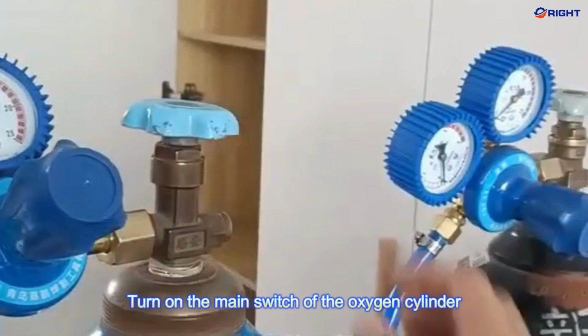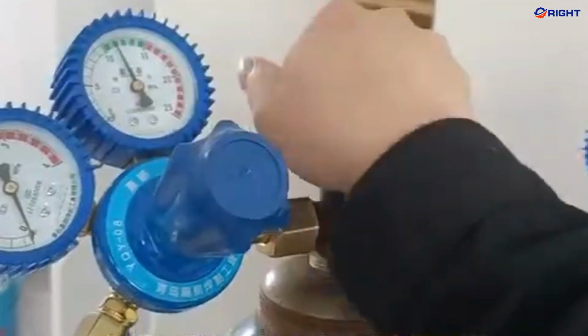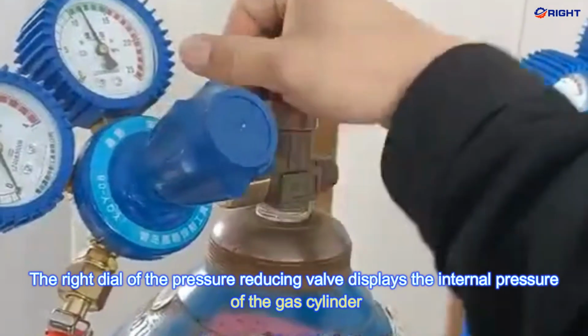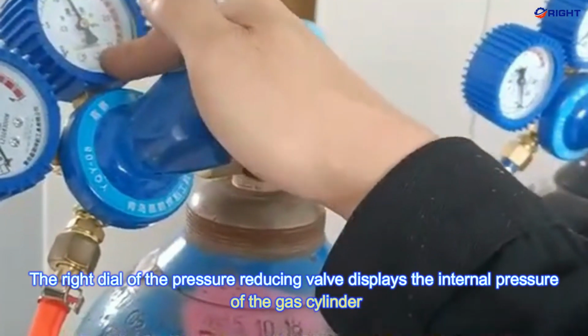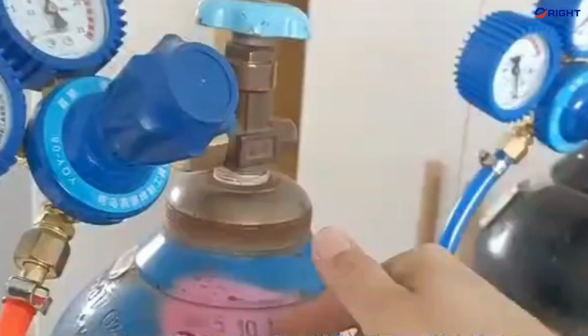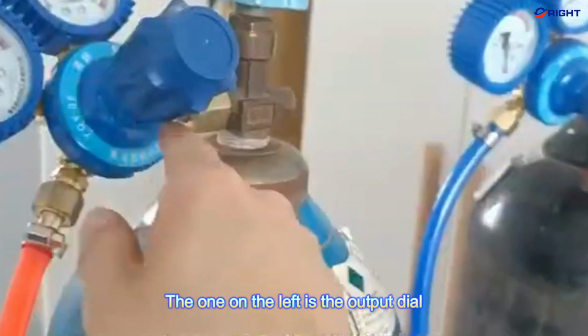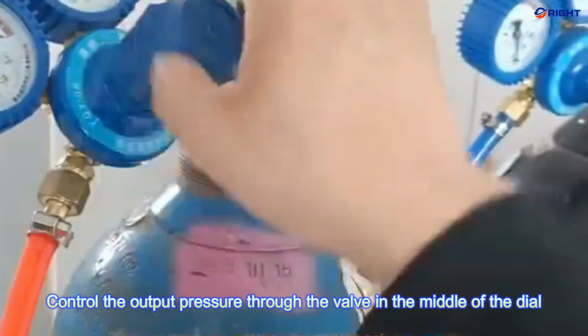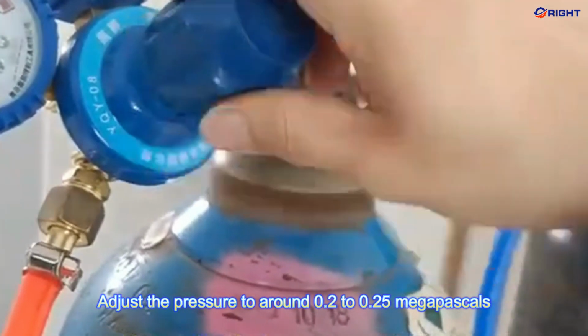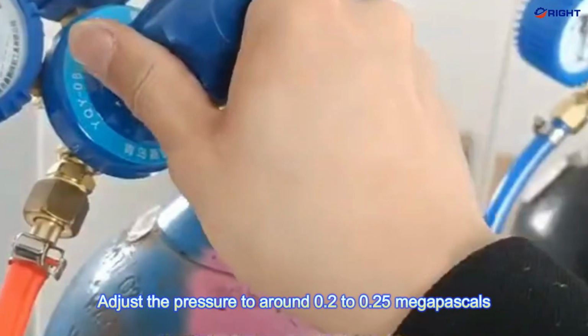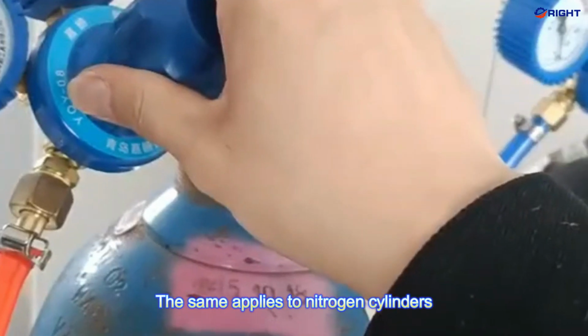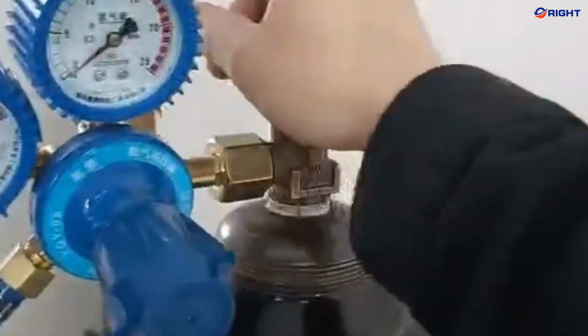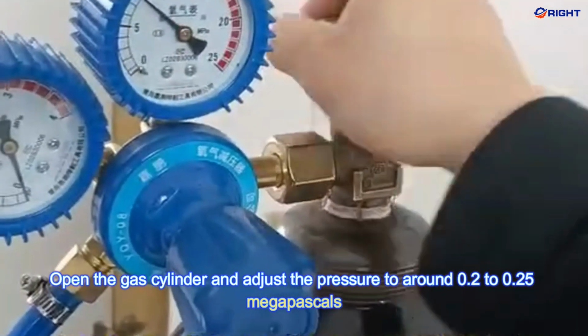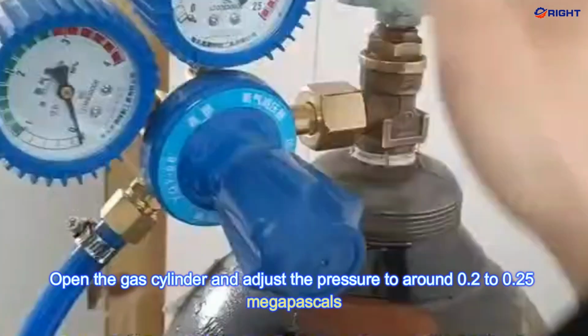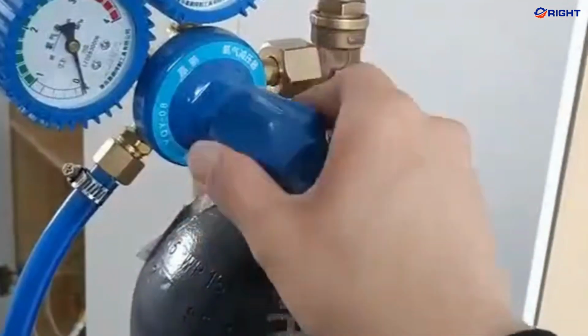Turn on the main switch of the oxygen cylinder. The right dial of the pressure reducing valve displays the internal pressure of the gas cylinder. The one on the left is the output dial. Control the output pressure through the valve in the middle of the dial. Adjust the pressure to around 0.2 to 0.25 megapascals. The same applies to nitrogen cylinders. Open the gas cylinder and adjust the pressure to around 0.2 to 0.25 megapascals.